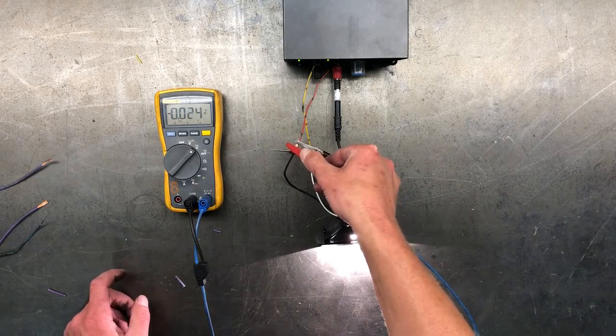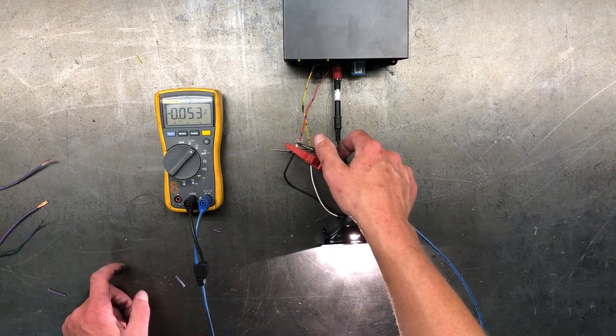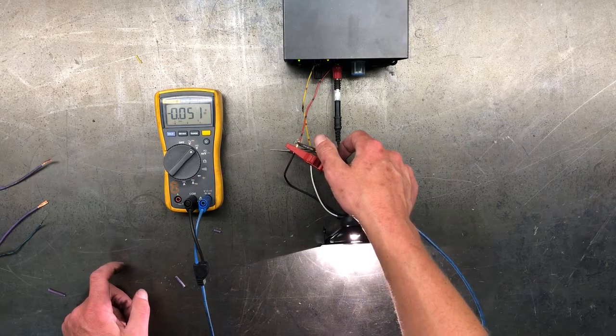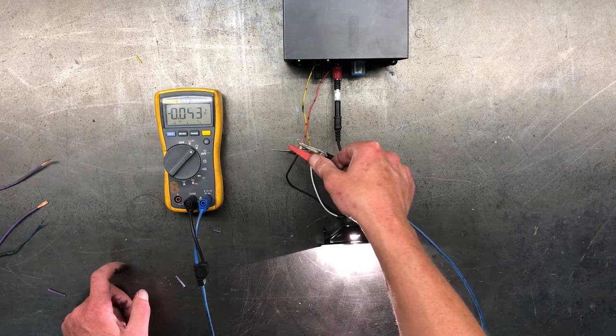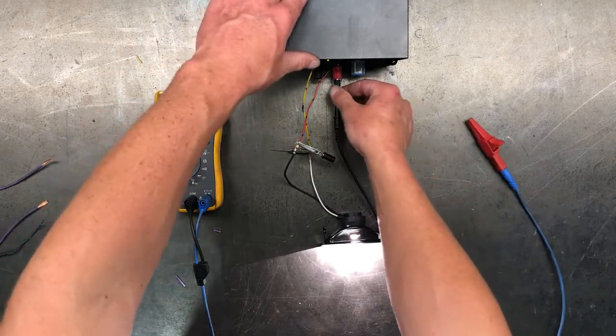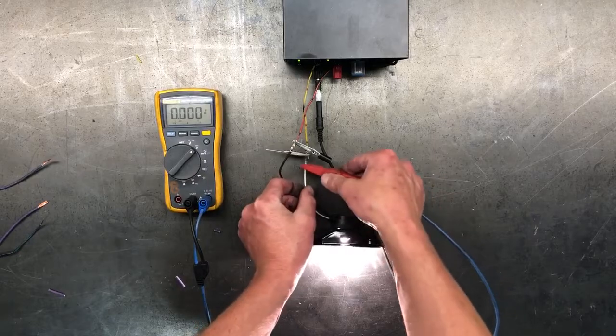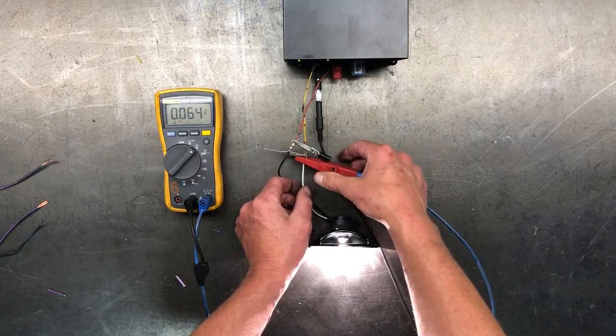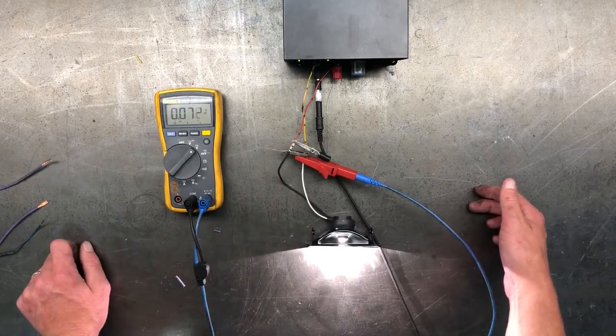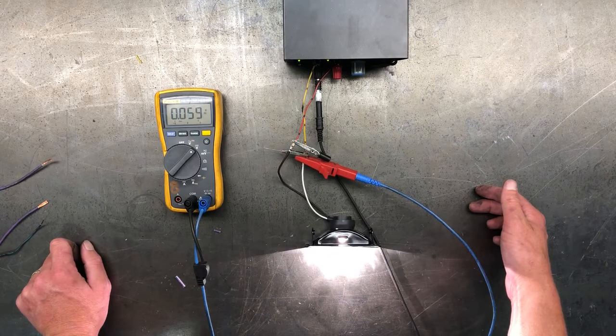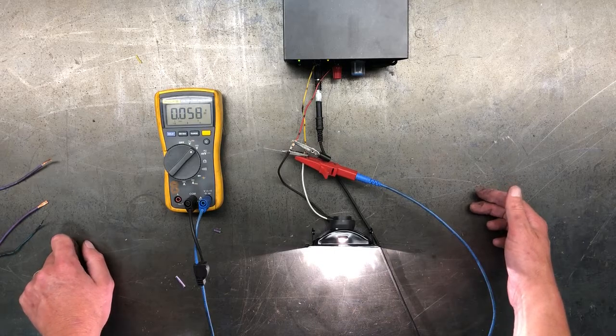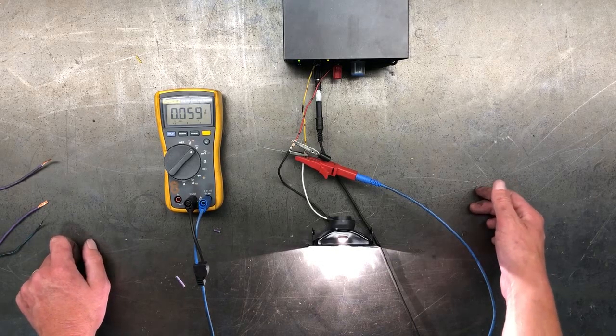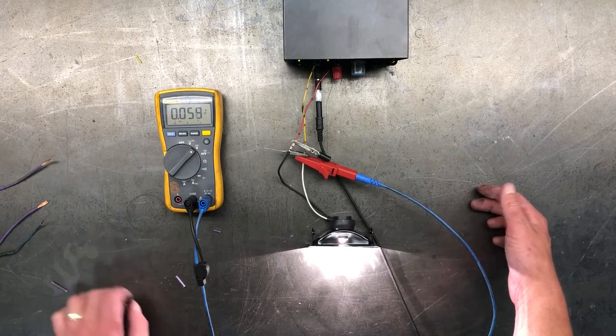So now when I go on here, we have a voltage drop of about 54 millivolts. So this wire is using 54 millivolts. Let's check our ground side. It looks like the ground is using about 60 millivolts. So there's about a 50 millivolt drop on the positive and a 60 millivolt drop on the negative wire.